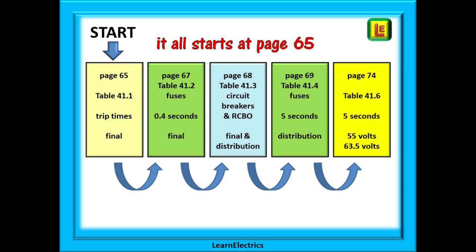Look at how this information flows. Page 65 is table 41.1 for disconnection times. Once you know the disconnection time, you can find the correct ZS table to use. Turn the page and you have table 41.2 for ZS values for fuses in 0.4 second final circuits. Turn the page again and there are the ZS values for circuit breakers and RCBOs in table 41.3. The ZS values in this table are for 0.4 second final circuits and for 5 second distribution circuits.